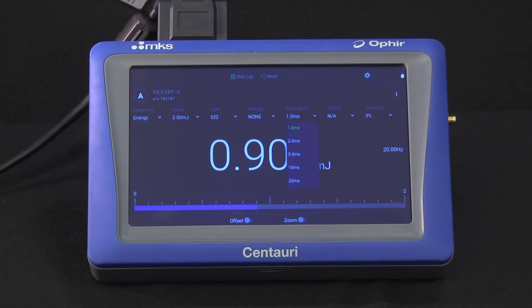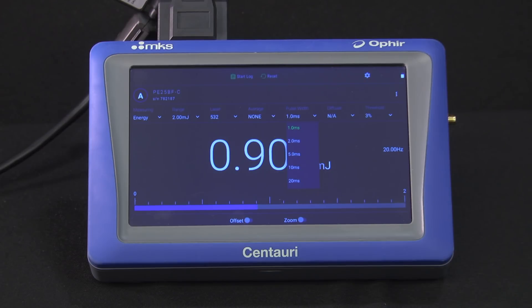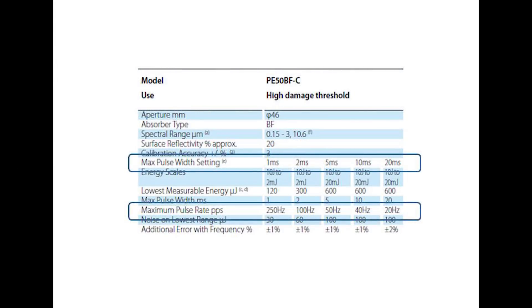Pulse Width. This sets the maximum pulse width — the time window during which a given pulse is integrated, held, and measured. Choosing a given maximum pulse width setting determines, of course, the maximum pulse repetition rate, as can be seen in the specifications.